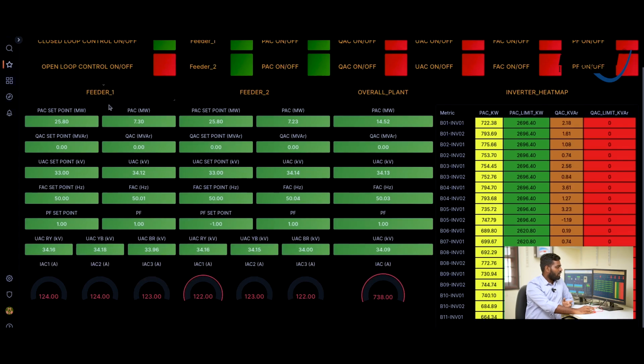In closed loop control mode, we have 5 control mode options: active power control, reactive power control, frequency control, voltage control and power factor control. And the operator can also check which mode is on and off. So you can check this screen, and this is the actual data of the active power, reactive power, power factor, voltage, feeder wise, and this is the operator set point limit. What are the set points set by the operator? Here we can check the active power limit set point, reactive power limit set point, voltage set point, power factor set point, and frequency. Similar to feeder 2 also.